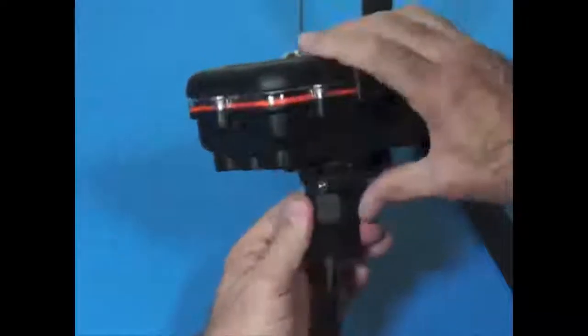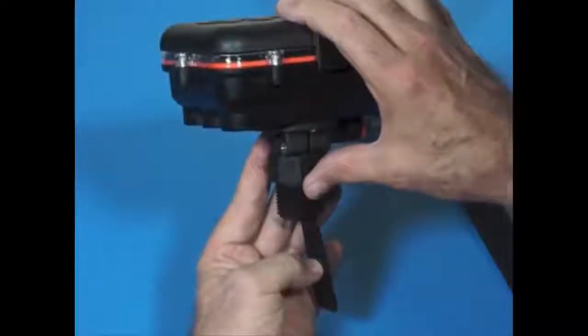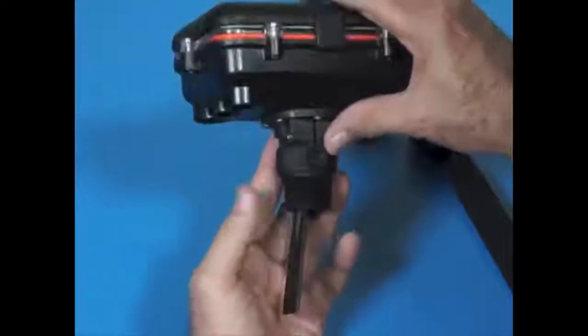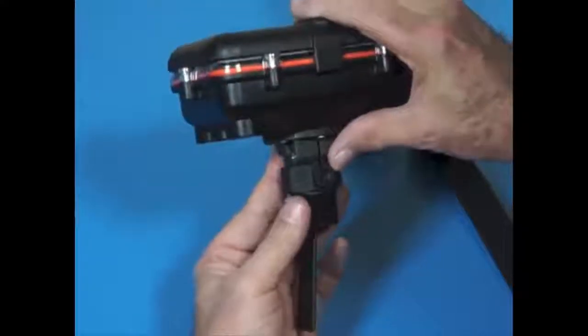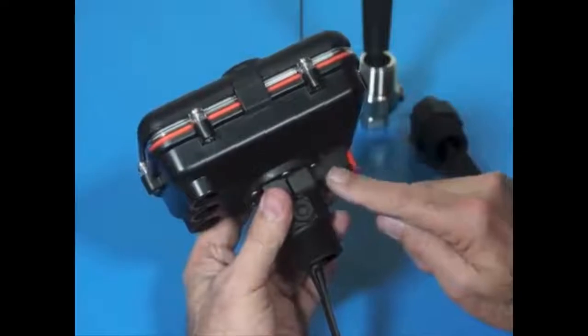So in use, flow pushes the paddle forward. This is sensed by the electrical head. The F29 then runs. If flow is lost, the paddle swings back to the off position and the pump is then shut down.